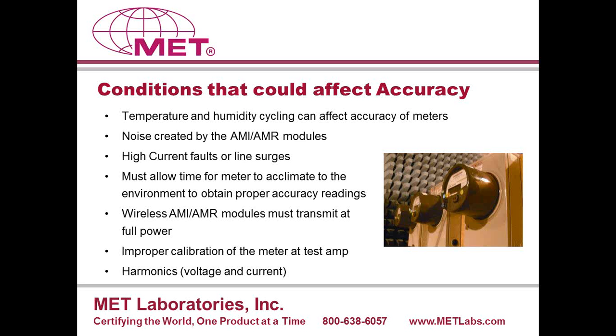Let's see, just a little bit more of the wireless modules. Again, you need to transmit at full power. When they are at full power, sometimes we'll see problems there. Improper calibration of the meter at test amps. That's something that we'll see right away. That's very rare, but on occasion we'll get it in and run a quick pre-test performance check on a full load, light load power factor and see that it's actually not in specification right away. Of course, if that happens, we notify the manufacturer right away and get some other samples in here. Typically, it's some anomaly that's caused that.